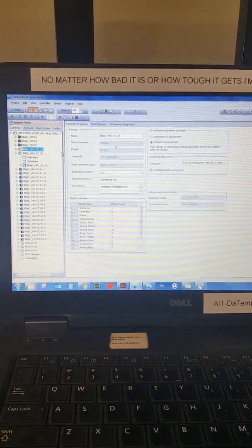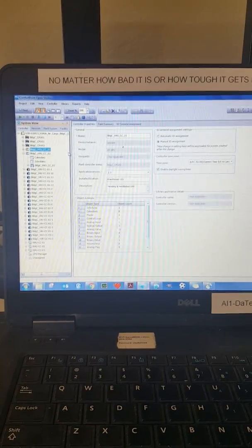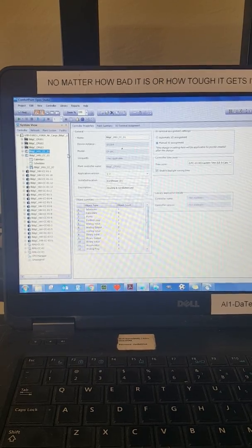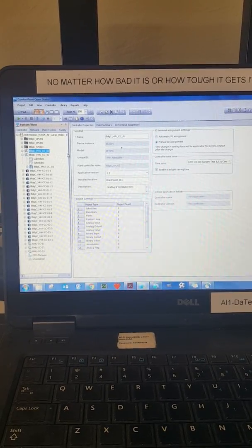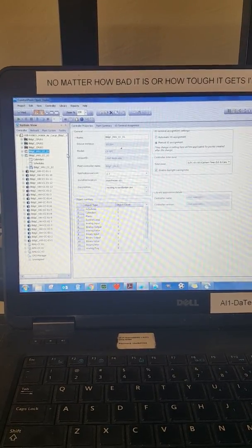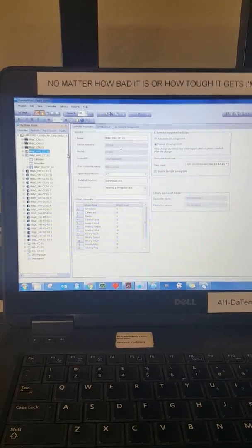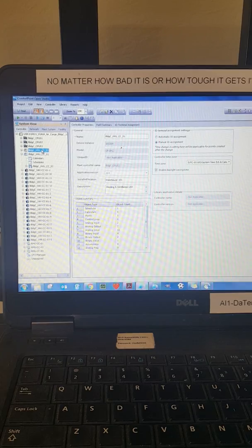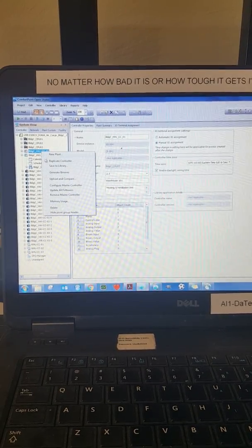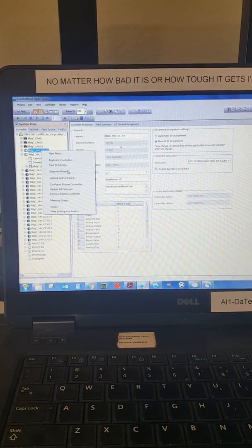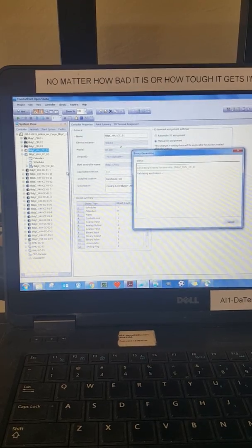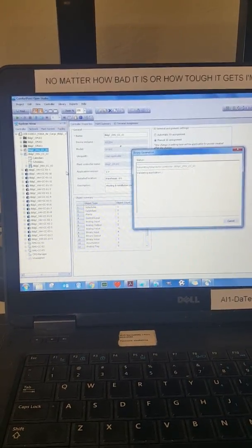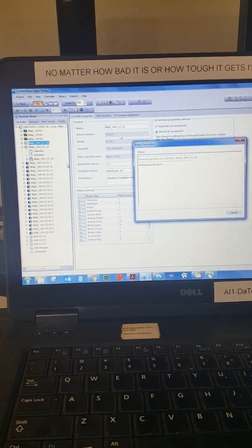but sometimes it's kind of hard to get specifications. So we're going to be specific with the ComfortPoint and how to upgrade firmware and download the database on a brand new unitary VAV controller. So first of all, inside the CPU, we're going to generate the binaries and send these to a folder, so when we go into the online tool, we can pull this database up, these binaries, and send it to the controller itself.